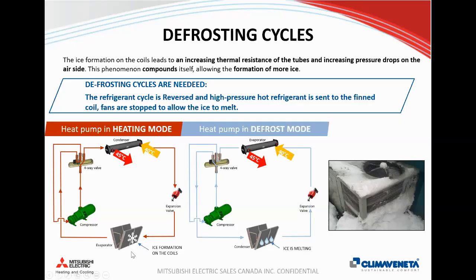So in order to extract heat from the outside ambient conditions, we need to supply refrigerant to that coil that's at a temperature colder than it is outside. And what can happen is, if it's damp or moist outside, you can get frost and ice that will actually condense and freeze to the coil because the coil's at a much lower temperature. So the way we manage this in defrost mode is we actually switch the unit into cooling mode.